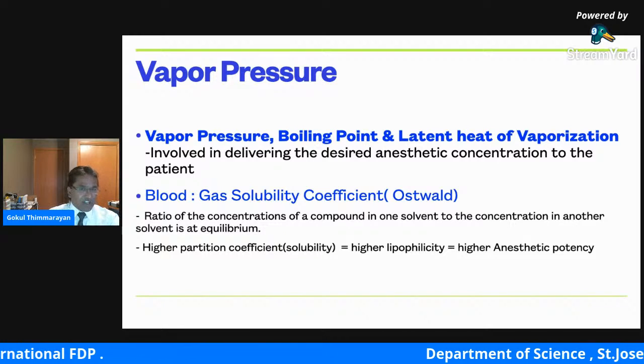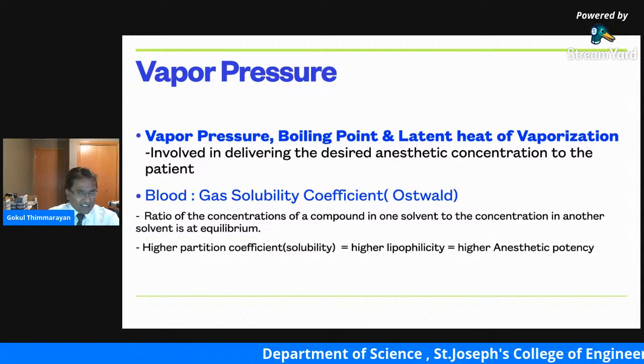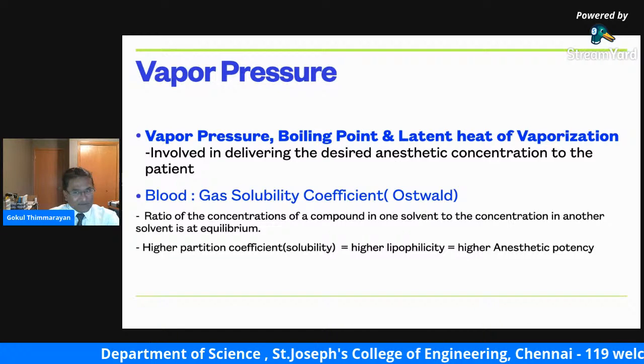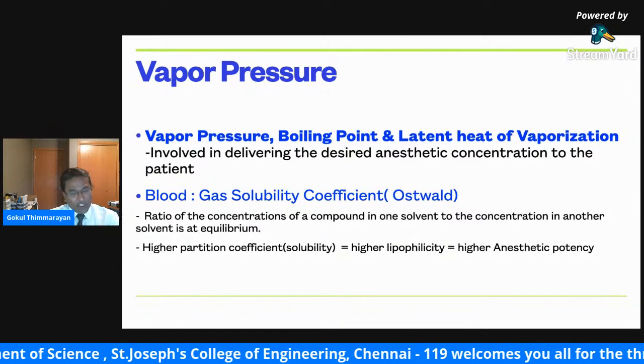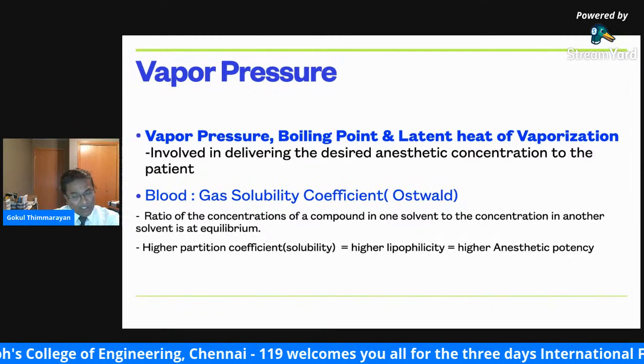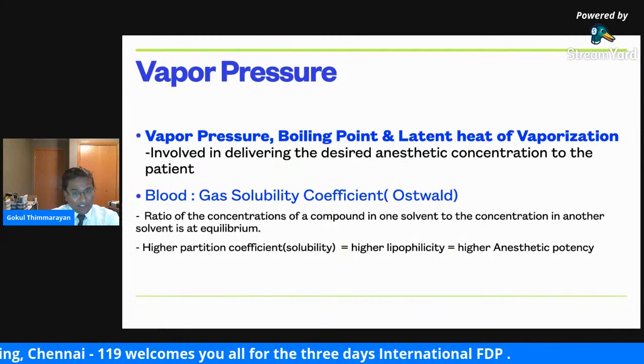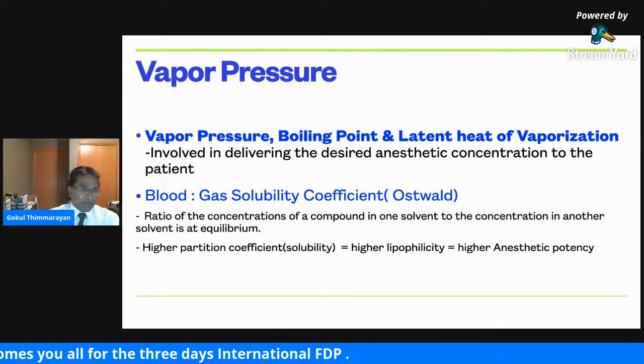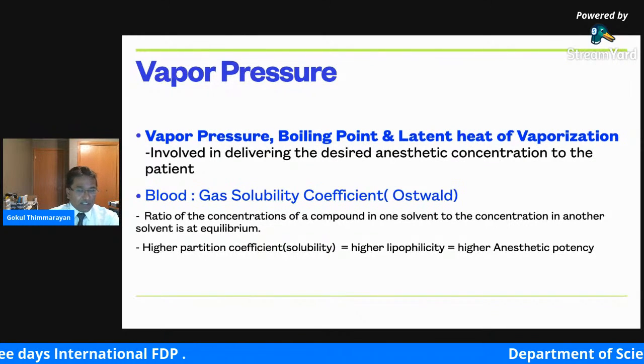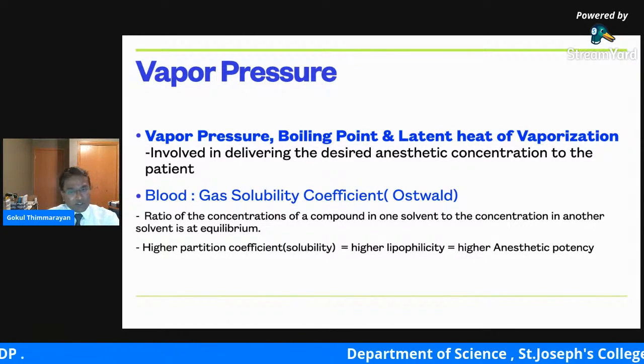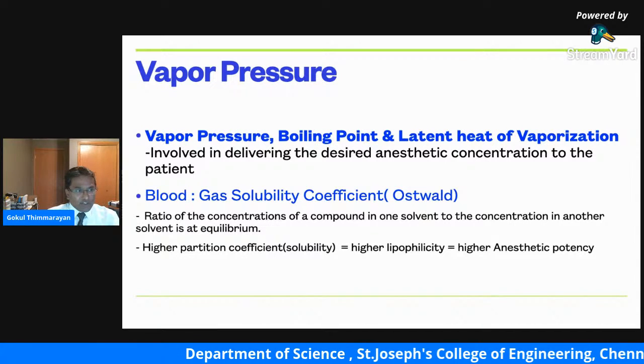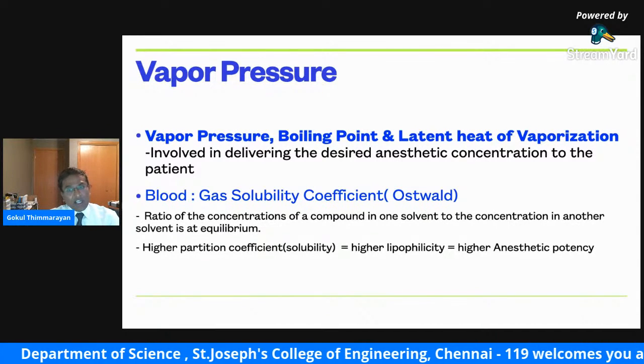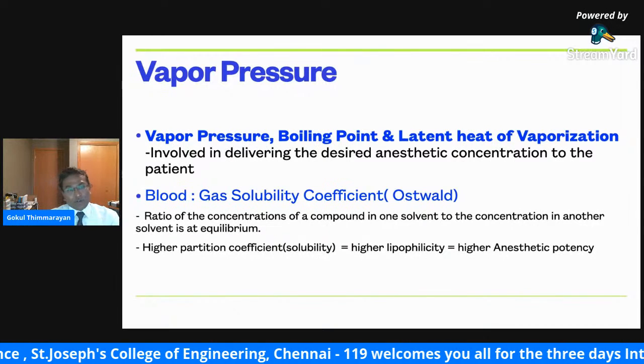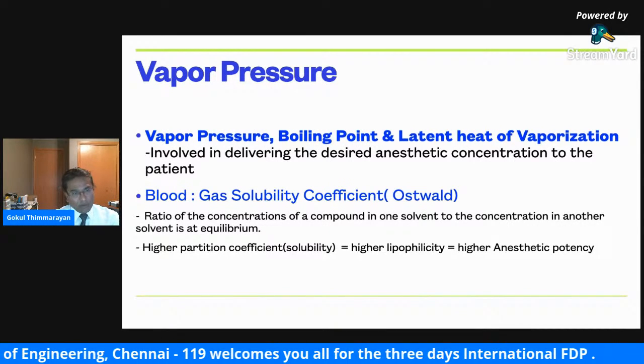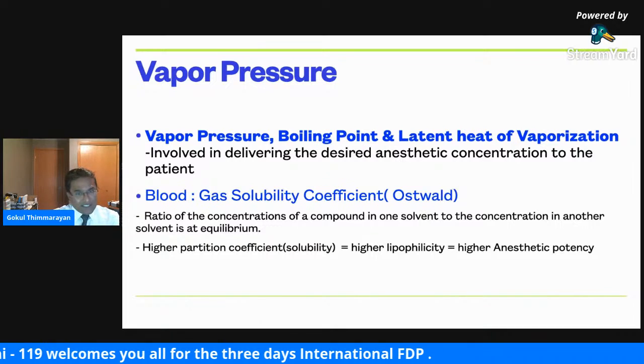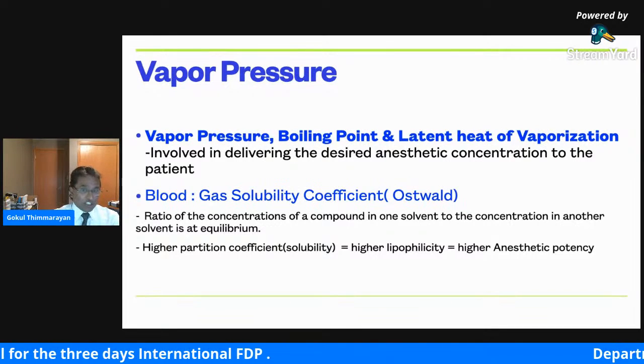And it's based on the vapor pressure, the boiling point of the inhalational anesthetic agent, and the latent heat of vaporization. All these physical principles are involved there to deliver exactly the right amount of anesthetic agent to reach the patient. If the vaporizer were not designed based on these principles, and we just had an inlet to let oxygen pass through it and carry some, a whole bunch of anesthetic agent would be delivered to the patient, and literally it could kill the patient. So to render safe anesthesia to the patient, the vaporizers are designed based on all these principles.